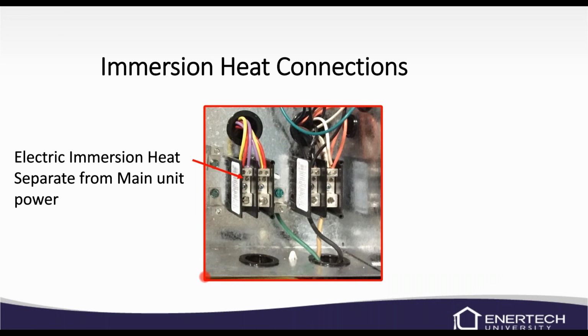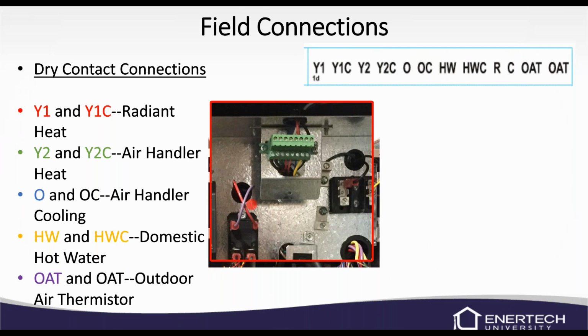Again, this is your immersion heater power block. We talked a little bit about these field connections here. These are basically your thermostat calls, to put it into regular terms, I guess. Basically, these are dry contacts. What dry contacts means is it just takes the contact closure. There's no power, there's no voltage between these.